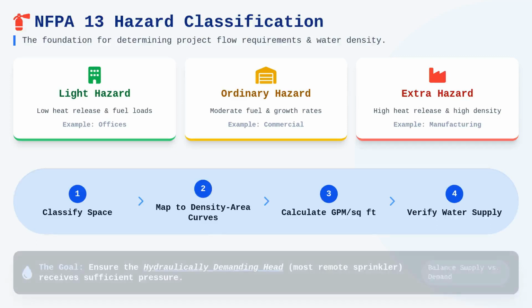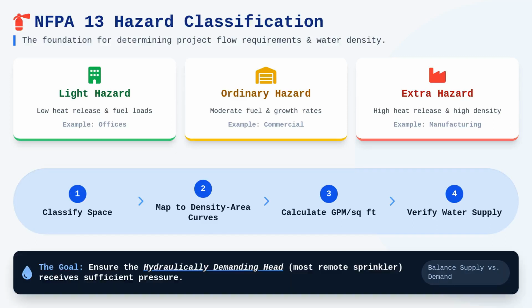We map these classifications to density area curves, which provide the minimum required water flow in gallons per minute per square foot over a specific design area. You must balance these requirements with the hydraulic capabilities of the water supply to ensure that the most remote sprinkler, often called the hydraulically demanding head, receives sufficient pressure.